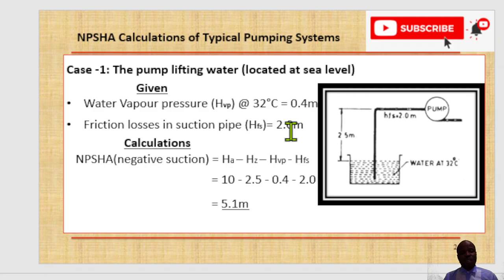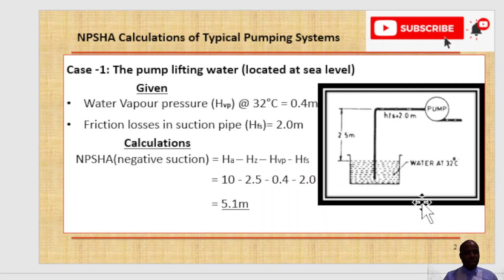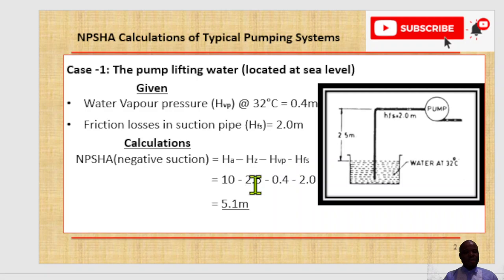Friction losses are the energy loss due to friction in your suction pipe — the sum of the fittings head loss and the straight run head loss. To obtain NPSHA for this negative suction system, the expression is: HA (the absolute pressure on the surface of the liquid in the supply tank, which in this case is atmospheric pressure converted to meters, giving 10 meters) minus HZ, the vertical distance between the surface of the liquid in the supply tank and the pump centerline.